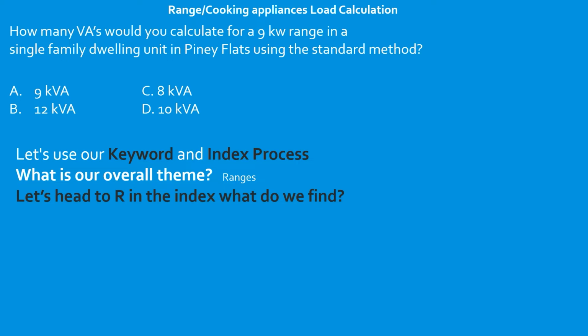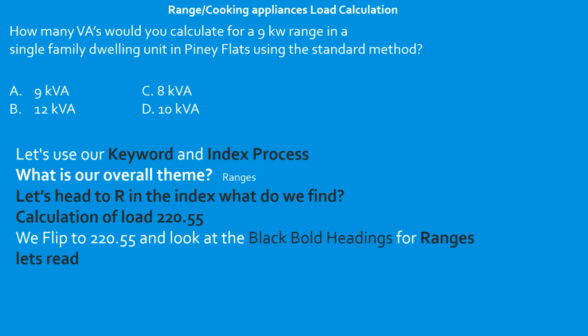Okay, so when we get there, first thing that we're going to do is we're going to always read the black bold heading. That lets us know whether or not we're in the right code section, because sometimes you can just misread it and think it's 230.55, and you get over to 230.55 and you start reading the paragraph and you're like, wait a second, this doesn't have anything to do with it. That's why as soon as you get to that section, make sure you read the black bold heading to make sure you're in the right article. So 220.55, it says electric cooking appliances in dwelling units. Bingo, I feel like we're in the right section.